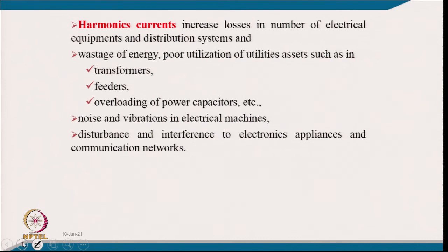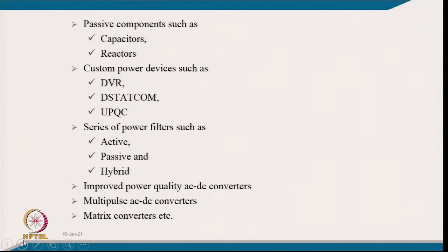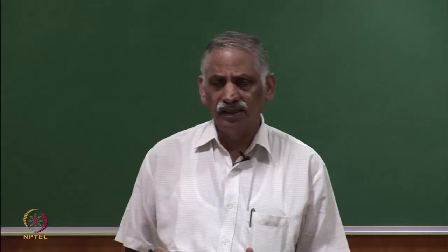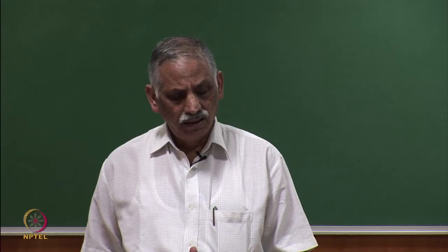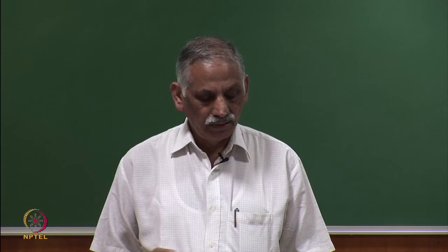Regarding classification of mitigation techniques for power quality problems: earlier, passive components like capacitors and reactors were used for reactive power compensation and negative sequence current compensation. Power quality improvement devices now include DVR — Dynamic Voltage Restorer — D-STATCOM, and UPQC. A series of power filters includes active, passive, hybrid, and improved power quality AC-DC converters with power factor correction at the input. For large-rating drives in the megawatt range, multi-pulse AC-DC converters or matrix converters are used at the input.